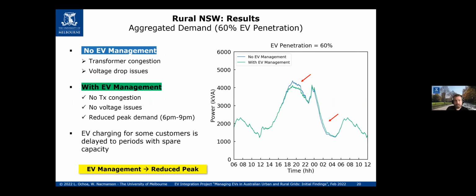Yes, thank you, Nando. As Nando pointed out, without EV management we can get significant congestion and voltage drop issues. Looking at the graph on the right, we show the net demand of the whole HV feeder, Hazelbrook, a rural New South Wales feeder. With EV management, we look to disconnect those charging points, cutting the problem off at the head, with the objective of managing transformer congestion and voltage issues, ultimately lowering that peak demand.